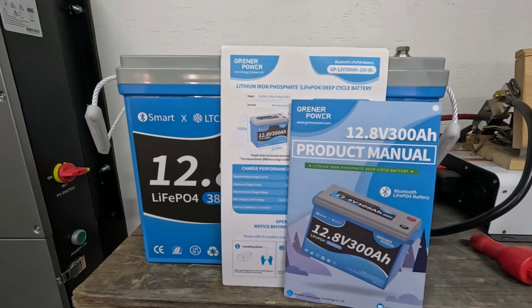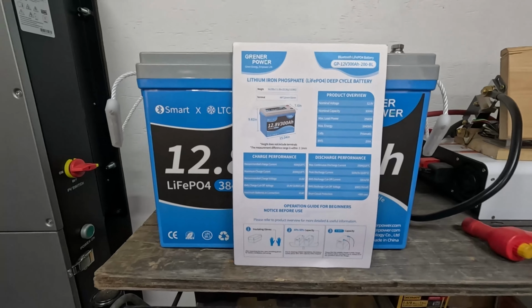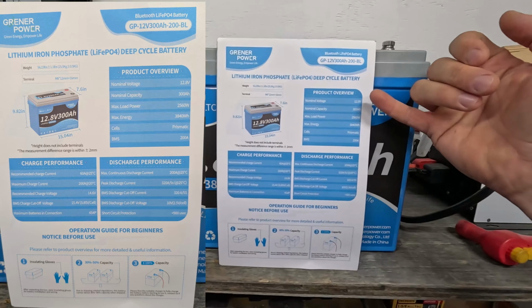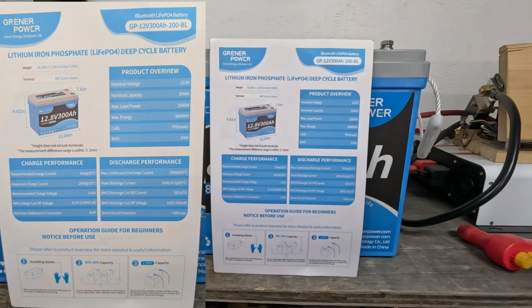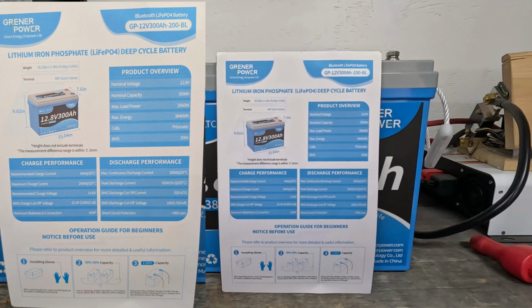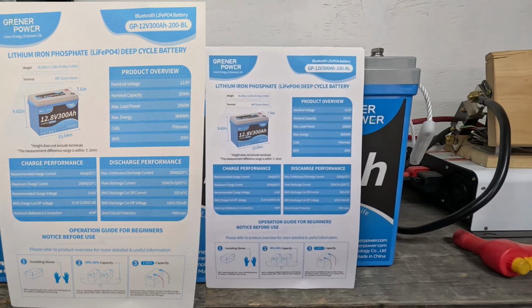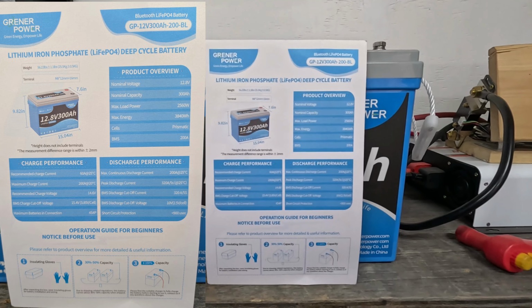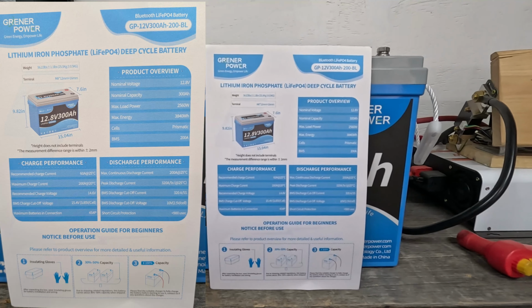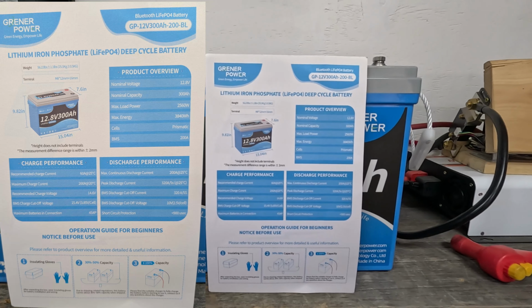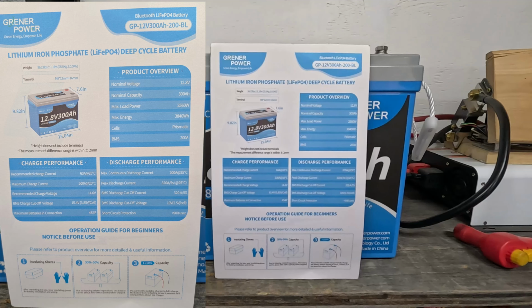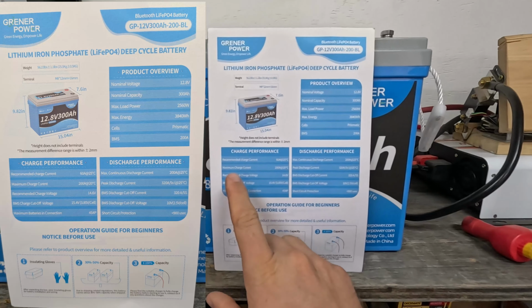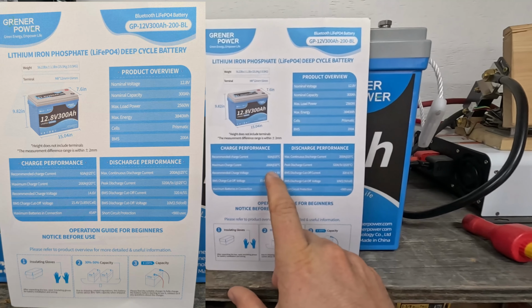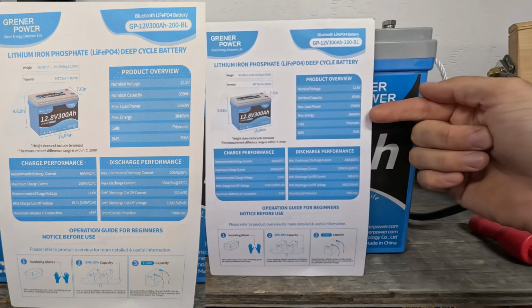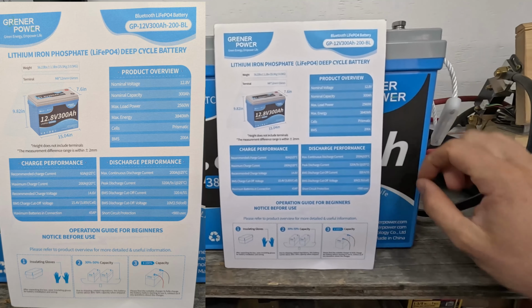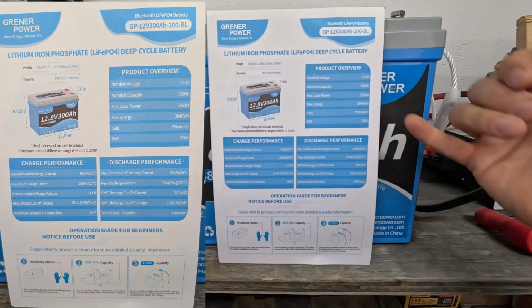So let's get started with the specification. Speaking of the specification, you can see here we have the nominal voltage, the capacity, we have the max load power, which they put here in watt, 2560. When we divide this by 12.8, we have 200 amps, so it says maximum charge current, that's also 200 amps. Then we have the maximum energy stored in this battery, 3840 watt hours, and we have prismatic cells.